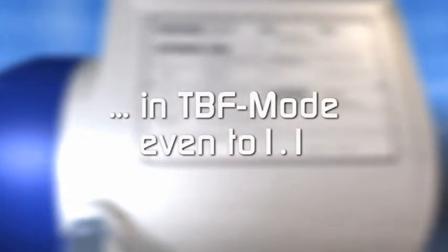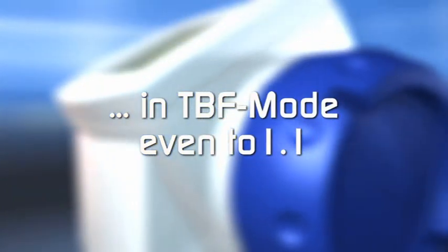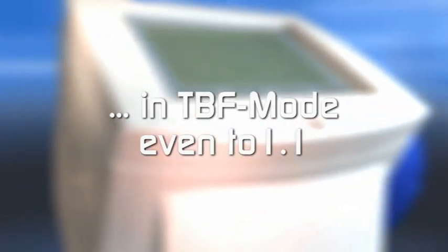The unique TBF mode, during which a reflection of the sensor end is traced, even enables products with a minimum relative permittivity of down to 1.1 to be measured.